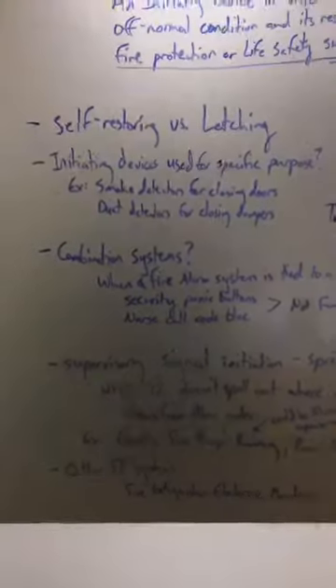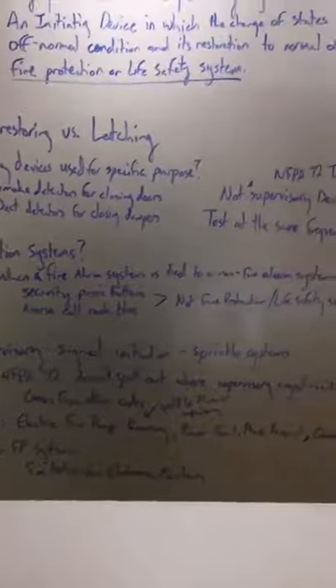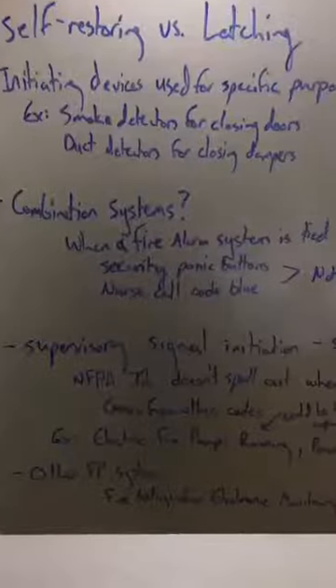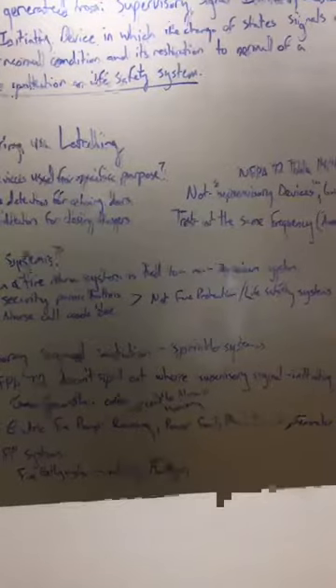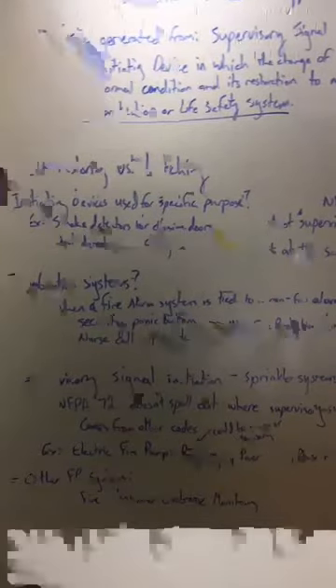What about combination systems? I get this question a lot. So when a fire alarm system is tied to a non-fire alarm system, it generates what's called a combination system. Examples of this are security panic buttons, nurse call code blue. Those are not fire protection life safety systems. I'm sure you're probably thinking code blue is not a life safety system. No, not from the perspective of what we talk about life safety systems being fire-related. So when an NFPA is talking about it, it doesn't cover code blue.